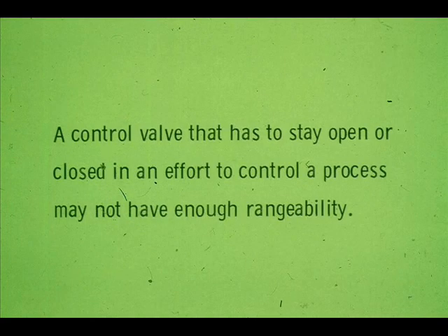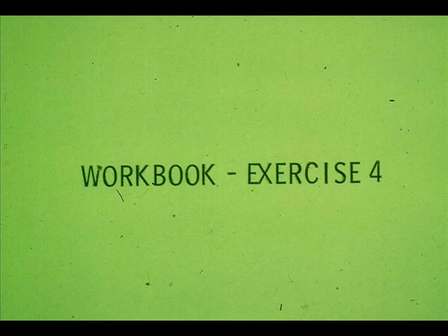Sometimes a control valve has to stay open or closed most of the time in an effort to control the process. This may indicate a valve malfunction, but often it means the valve is being used out of its effective controlling range. Now, work exercise 4 in your workbook.